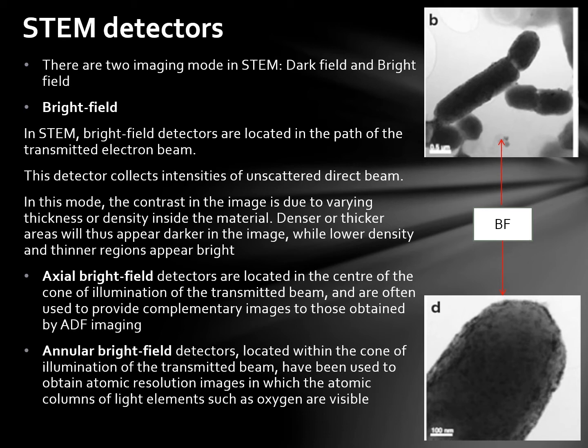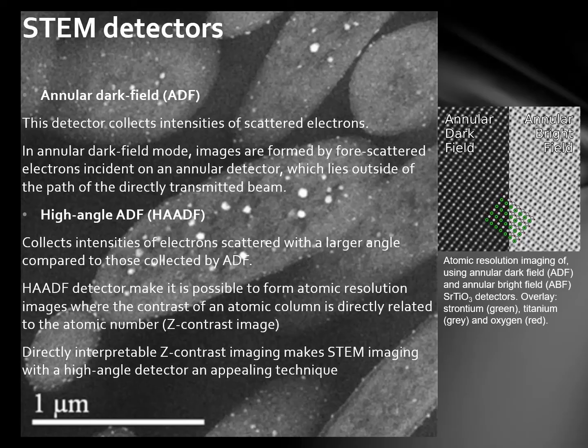Annular bright field detectors located within the cone of illumination of the transmitted beam have been used to obtain atomic resolution images in which the atomic columns of light elements, such as oxygen, are visible. ADF detectors collect intensities of scattered electrons. In annular dark field mode, images are formed by scattered electrons incident on an annular detector which lies outside the path of the directly transmitted beam. High angle ADF collects intensities of electrons scattered with a larger angle compared to those collected by ADF. HAADF detectors make it possible to form atomic resolution images where the contrast of an atomic column is directly related to the atomic number.